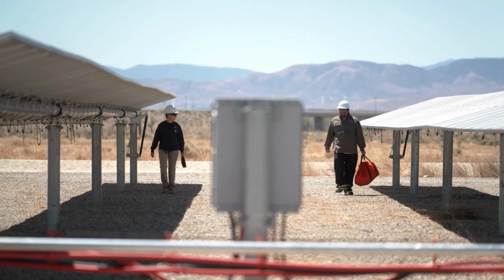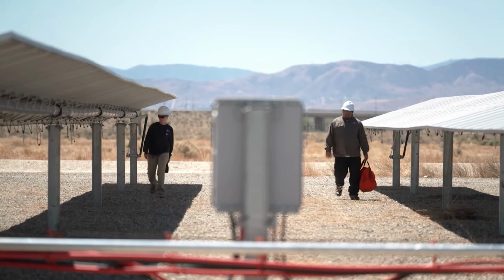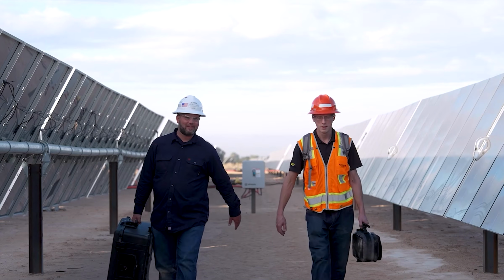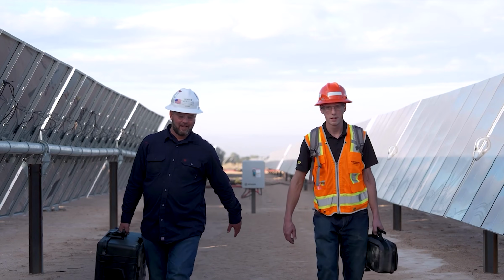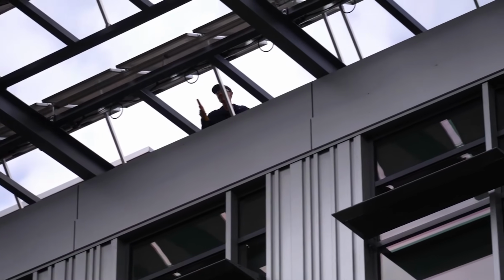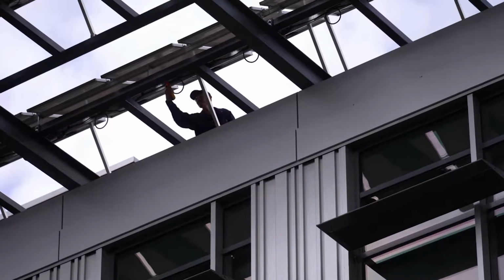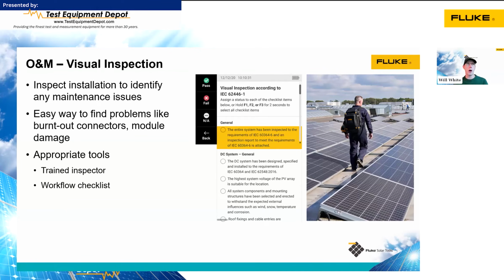A good technique during operations and maintenance is visual inspection. This is actually required by that IEC standard, and we're looking to see if there's any issues with the system. If you are trained and know what you're looking for, you can find all kinds of different issues like burnt out connections, damaged modules. You can find issues with racking. Obviously, something like a missing label would be pretty easy to see.